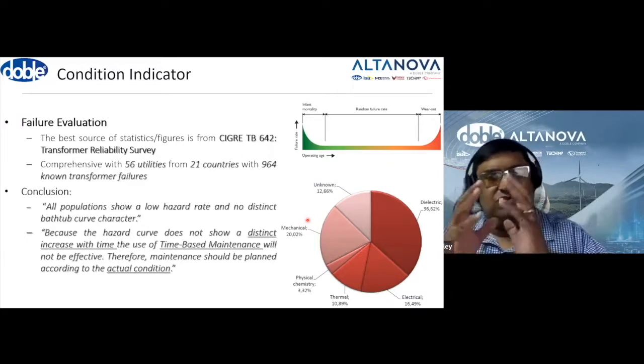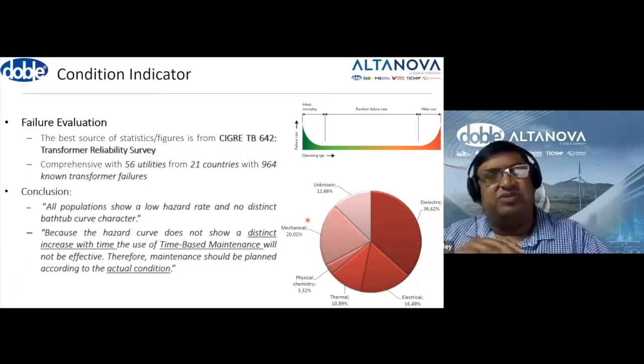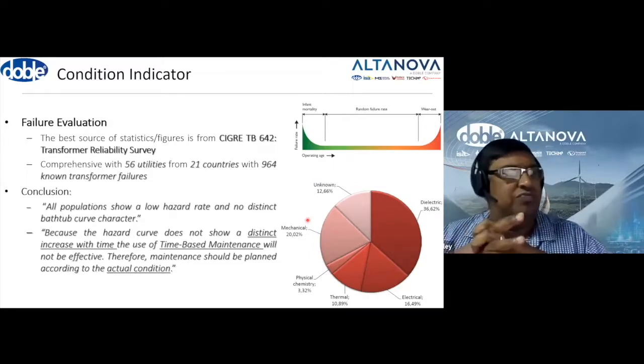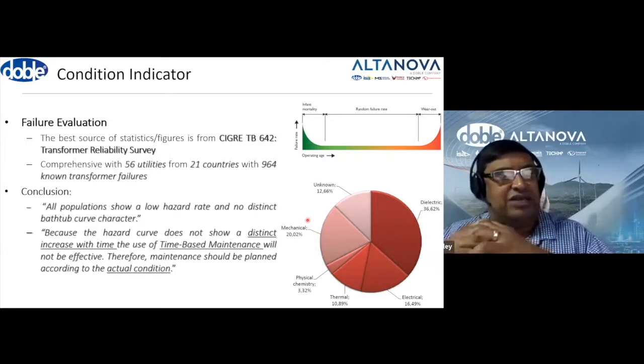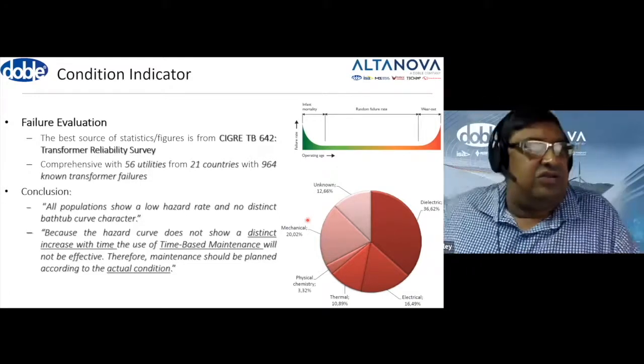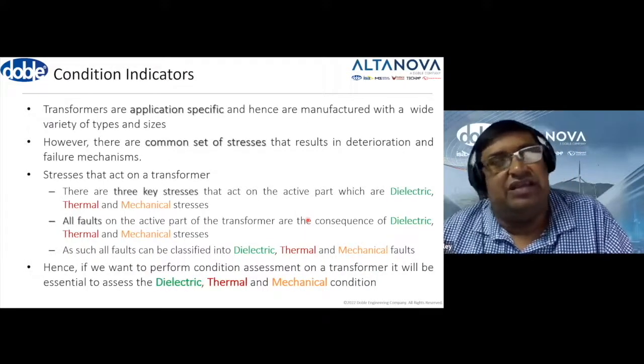All right, so one conclusion drawn from this document was that the failure pattern of transformers doesn't generally follow the bathtub curve, which is an important part. It also emphasizes the fact that time-based maintenance, which I think is something we all know, really doesn't work. You need to move more onto the condition of the transformer than anything else. Like many organizations, CIGRE also puts out different types of failure classifications, which can be used as your condition indicators, right?